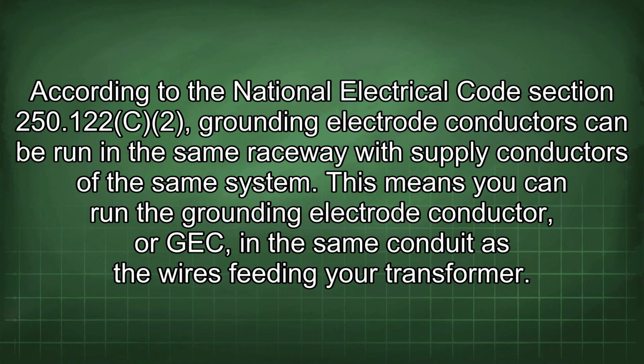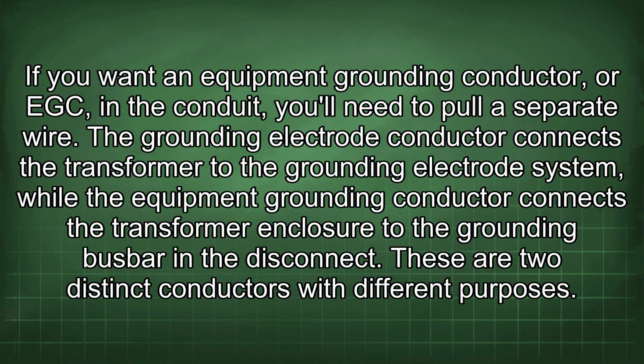According to the National Electrical Code Section 250.122(c)(2), grounding electrode conductors can be run in the same raceway with supply conductors of the same system. This means you can run the grounding electrode conductor, or GEC, in the same conduit as the wires feeding your transformer. If you want an equipment grounding conductor, or EGC, in the conduit, you'll need to pull a separate wire.